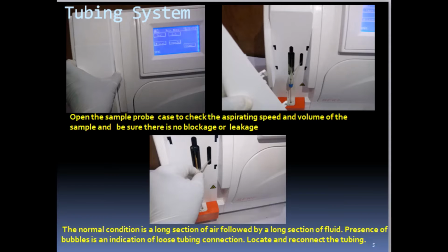For the maintenance of the tubing system, the first thing to do is to open the sample probe case to check the aspirating speed and volume of the sample and be sure there is no blockage or leakage. The normal condition is a long section of air followed by a long section of fluid. Presence of bubbles is an indication of loose tubing connection. Locate and reconnect the tubing.